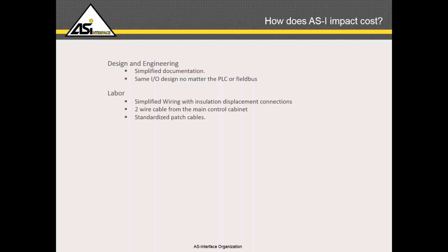Labor is a big part of the cost factor when you're looking at the AS-i impact. Again, simplified wiring with insulation displacement technology. The nice thing is being able to snap I/O onto the flat cable like Lego pieces, and be able to remove and modify them easily to move I/O modules to different locations without having to unwire and rewire, or re-pull wire to different locations. You can run just a 2-wire flat cable from the main control cabinet instead of big wiring bundles or harnesses required for hardwired systems, and use standard patch cables for all I/O connections instead of running everything through terminal strips. Those are all things that impact the labor of the machine.